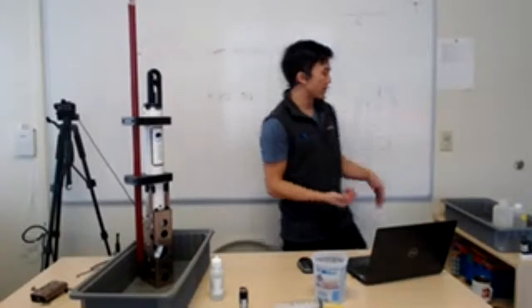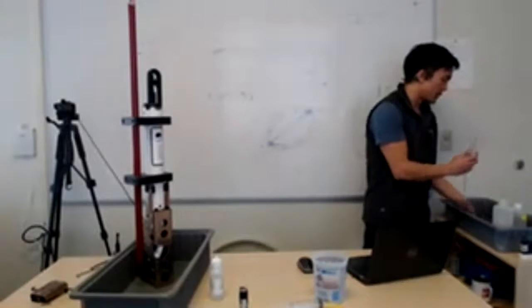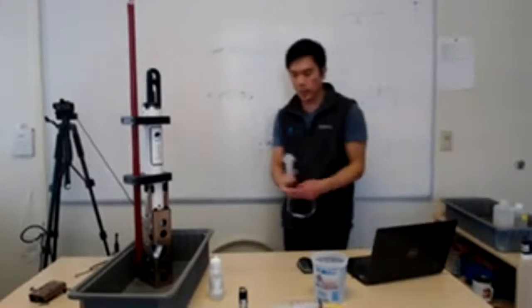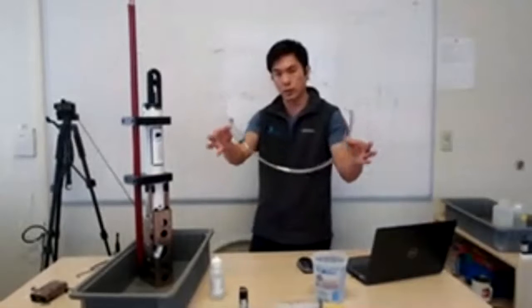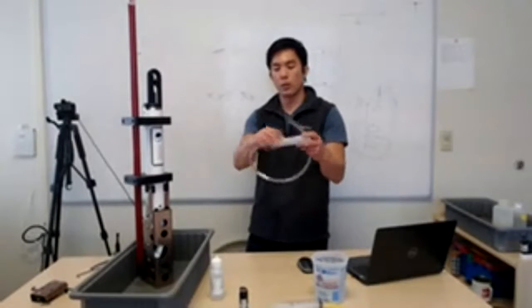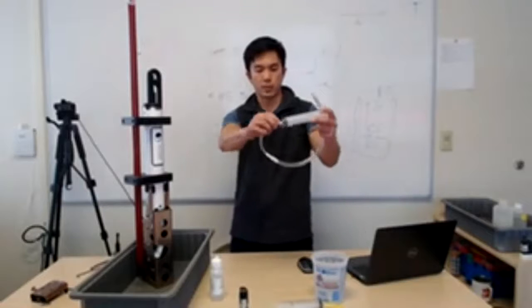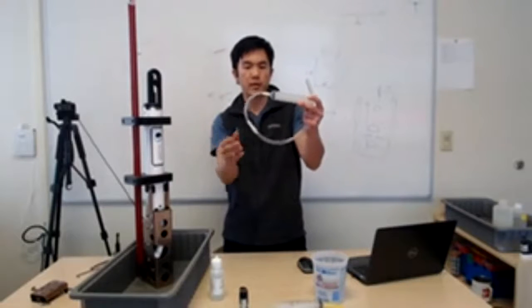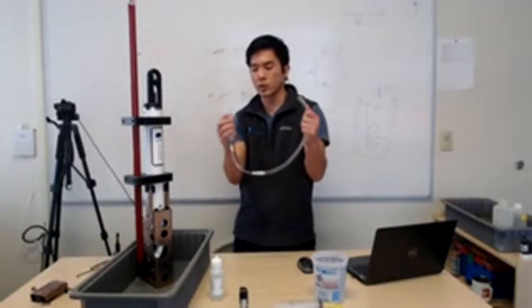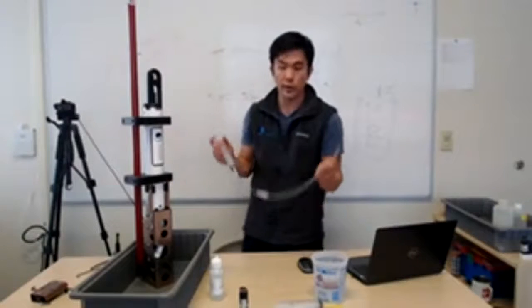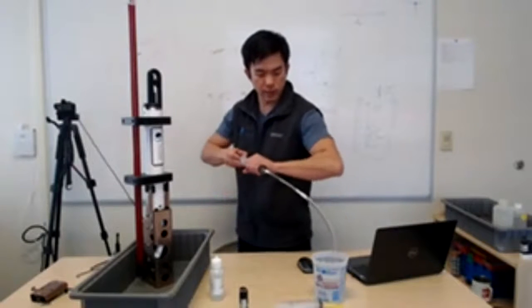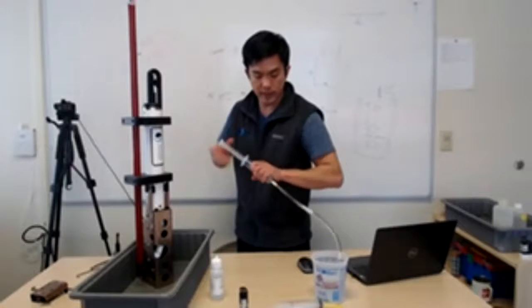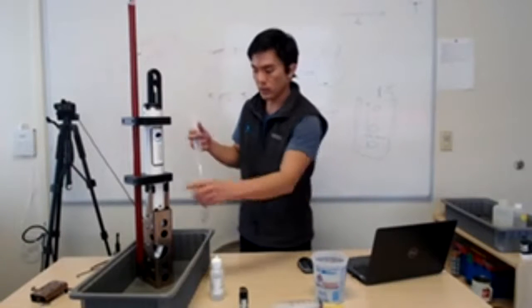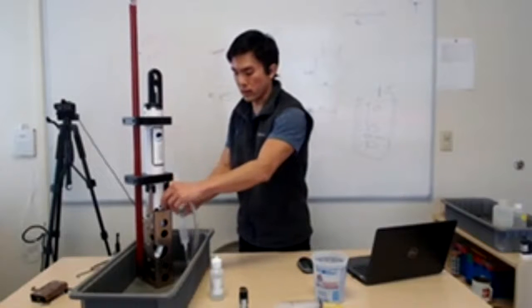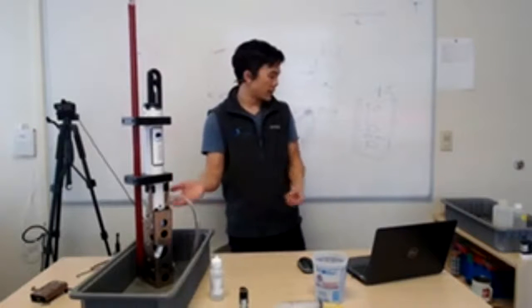Okay, now I'm going to demonstrate the flushing procedure, but the cleaning procedure is very similar. We have some videos for how to do this on our YouTube channel. Basically, what you're going to do is take this syringe that's provided with your HydroCAT EP, where you have your syringe, this piece right here, this smaller piece of tubing that connects to this plastic piece to the larger piece of tubing that connects to the hose barbs on your instrument. Pretty simple. You're just going to fill this up with clean, fresh water, clean, deionized water. Put this onto one of the connectors here.